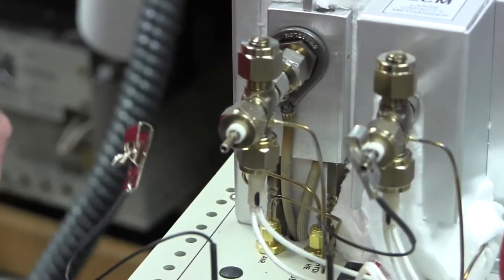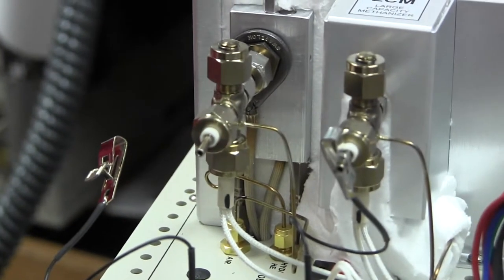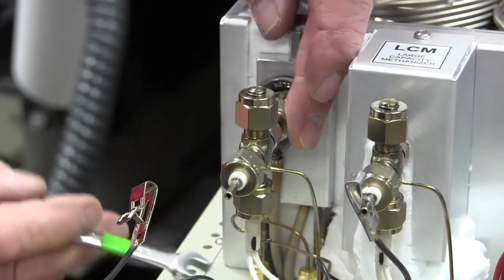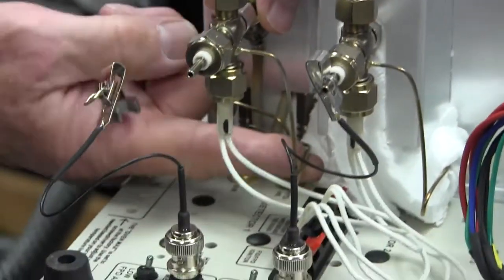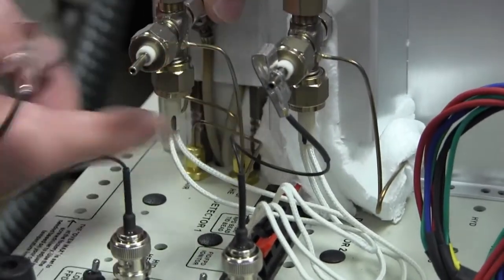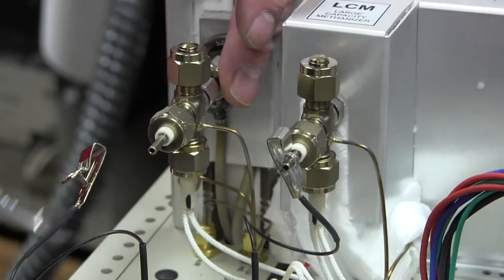It would be easier if we could remove that. We need to remove the air connection. Down here there's a tube running from the air bulkhead up to the FID detector and we need to remove that.